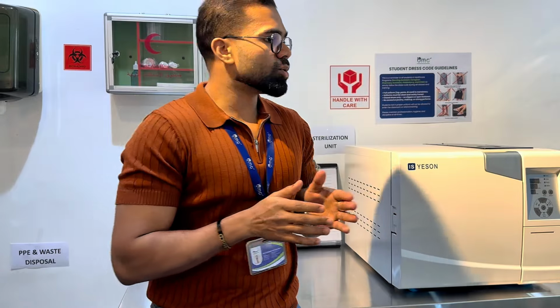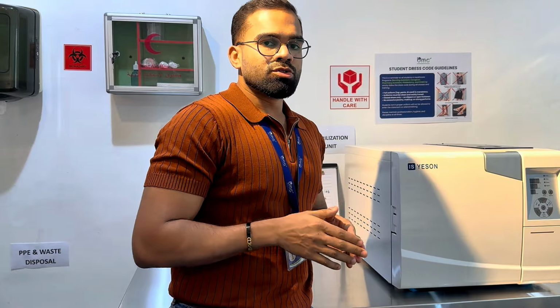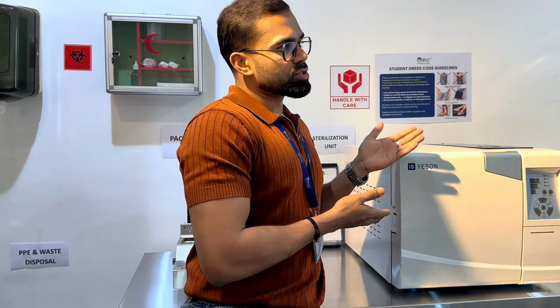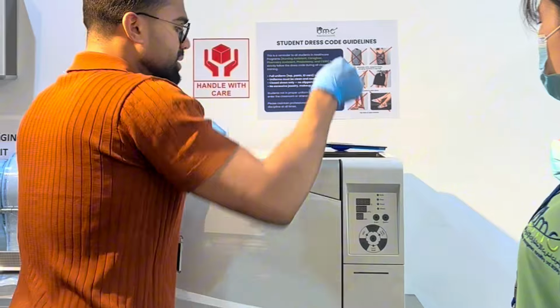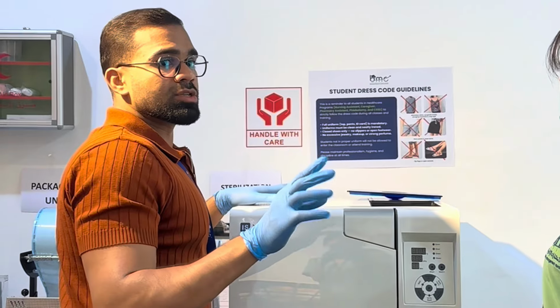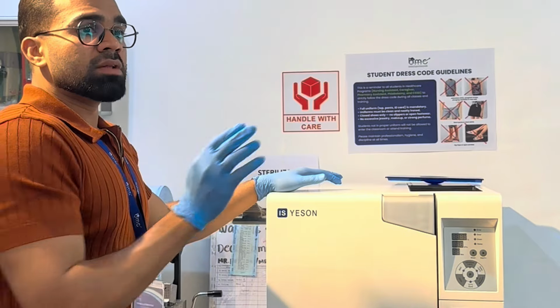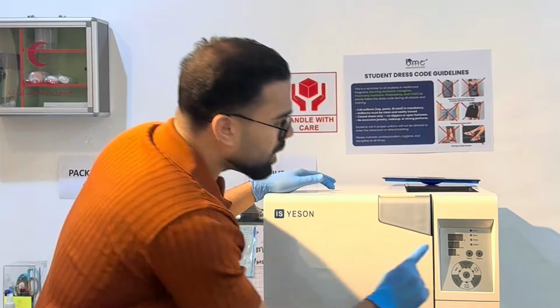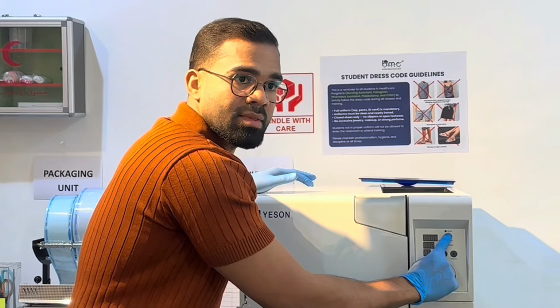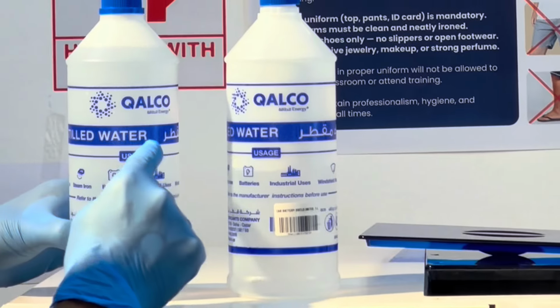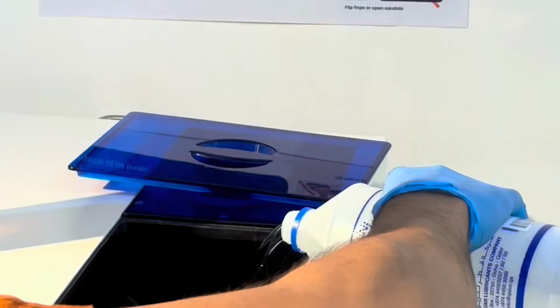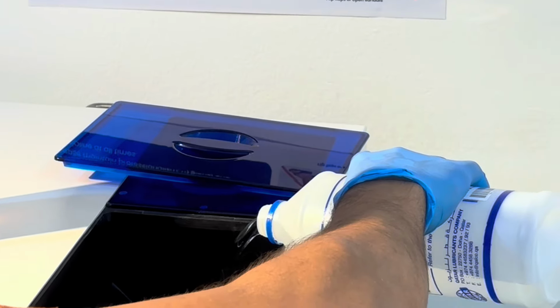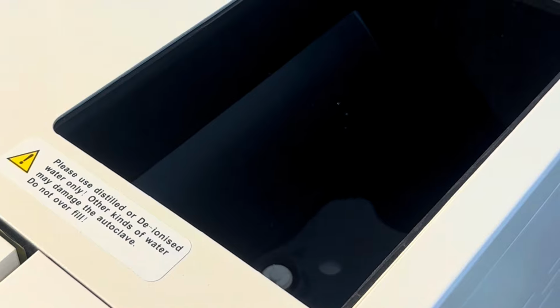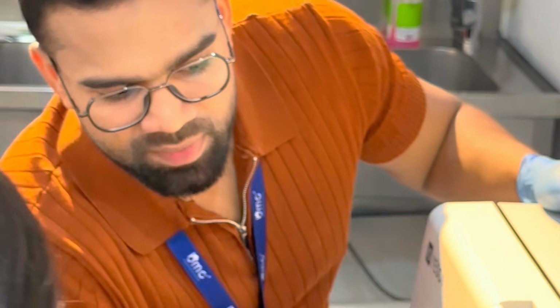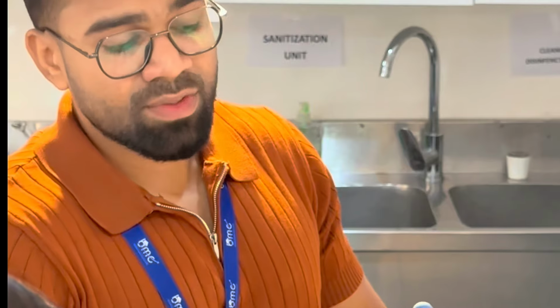Next, set the required temperature and pressure according to the type of instruments being sterilized. Carefully monitor the cycle parameters before starting the process. Once the cycle is initiated, maintain observation until completion. Pour distilled water carefully to avoid contamination. Then, check and confirm the water level is correct. With the water level confirmed, then close the chamber cover securely to initiate the sterilization, and properly document it for quality assurance and compliance.